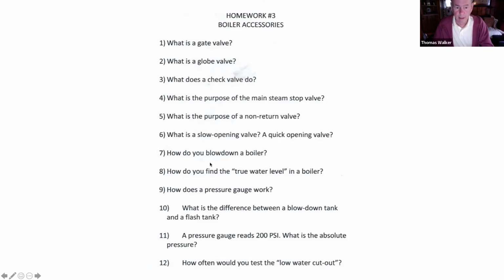Right? How do you blow down a boiler? Can't help you there, you've got to remember that procedure. All right. How do you find the true water level in a boiler? All right. When they ask you, how does a pressure gauge work? What's the key word they're looking for? A Bourdon tube. All right. If you can tell them a Bourdon tube, you've got it half licked. All right. The difference between a blowdown tank and a flash tank. Remember that one. Blowdown tank makes no attempt to recover the heat in the blowdown. It simply cools the water before it discharges it to sewer. The flash tank tries to recover the heat otherwise lost in the blowdown.